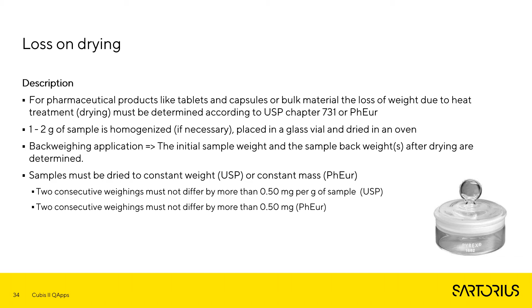Also for the loss on drying procedure, of course, the user is guided through a workflow and measures at first the initial sample weight and then up to 3 back weights. The software automatically calculates the results and evaluates if a sample is in compliance according to USP or to the European Pharmacopoeia. So whenever the sample weight is out of limits, then the user gets a notification that the test is failed, as shown here in the screenshot on the right-hand side. If the weight difference is too high, the user gets a message screen displayed.